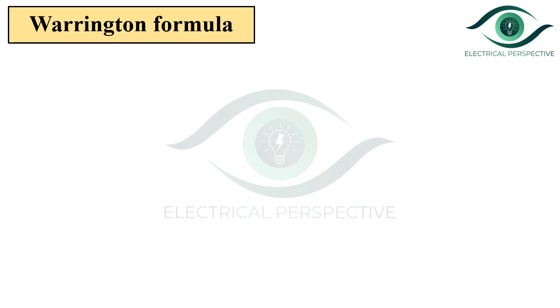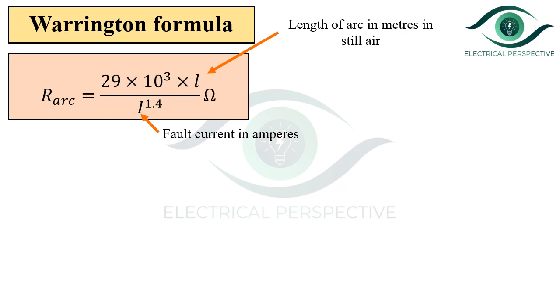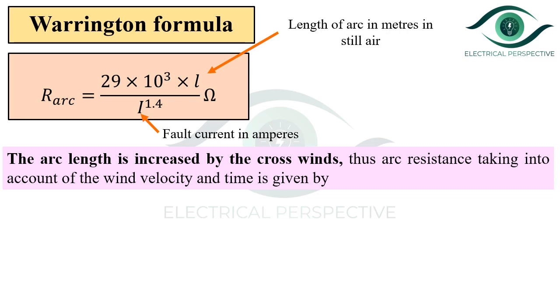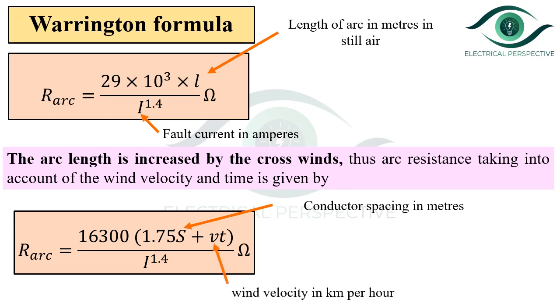The arc resistance is given by the Warrington formula. Here, L is the length of arc in meters in still air — meaning the air is stationary with no motion — and I is the fault current in amperes. The arc length is increased by crosswinds. Thus, the arc resistance taking into account wind velocity and time is given by a second formula, where S is the conductor spacing in meters, V is the wind velocity in kilometers per hour, T is the time in seconds, and I is the fault current in amperes.